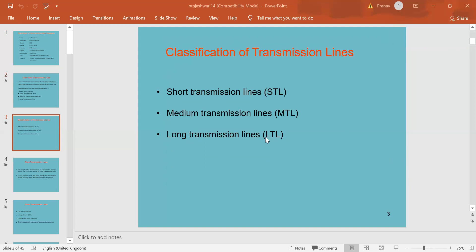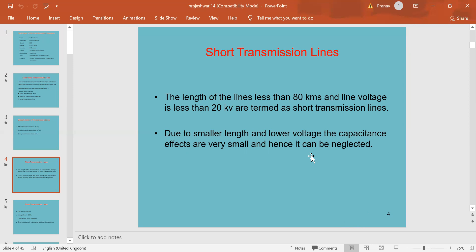Coming to a short transmission line, the length of the line is less than 80 kilometers and line voltage is less than 20 kilovolts. Due to the smaller length and lower voltage, the capacitance effects are very small and hence neglected. So those lines are called short transmission lines, and in these lines we neglect the capacitance effect because of small length and lower voltage.